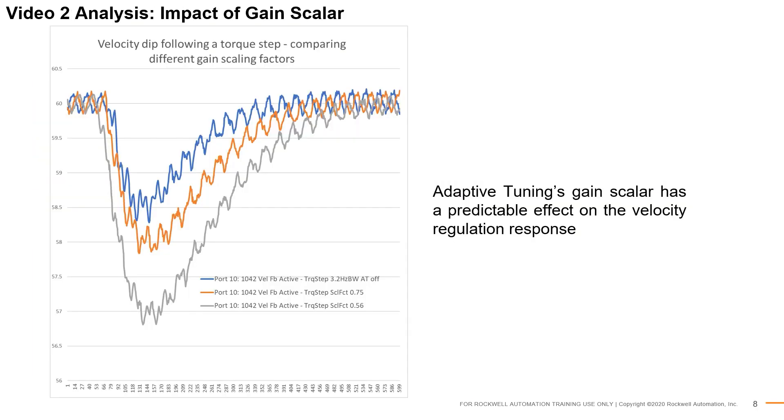We can observe the effects of the gain scalar by studying the velocity tracking performance in response to a torque load step. Once adaptive tuning updates the gain scalar, the value is retained and a load step is applied. In the comparisons below, we see the velocity dip resulting from the load step. The blue trace represents the system response when the gain scale is 1. Now let's look at the orange trace. When the gain scalar is detuned to 0.75, the effective system bandwidth is reduced. This results in a larger velocity dip and a longer settling time.